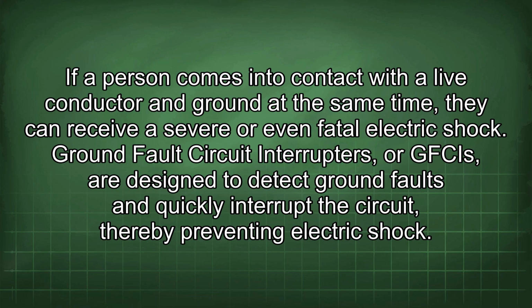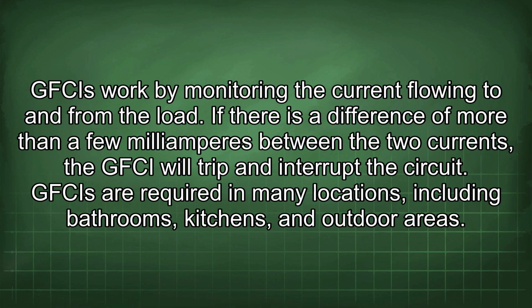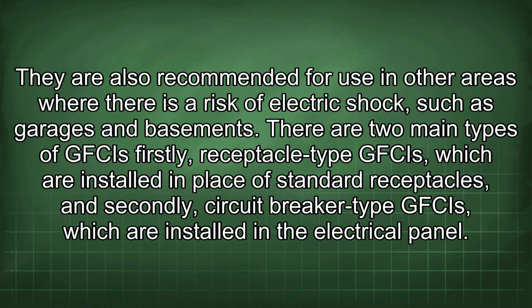Ground fault circuit interrupters, or GFCIs, are designed to detect ground faults and quickly interrupt the circuit, thereby preventing electric shock. GFCIs work by monitoring the current flowing to and from the load. If there is a difference of more than a few milliamperes between the two currents, the GFCI will trip and interrupt the circuit. GFCIs are required in many locations, including bathrooms, kitchens, and outdoor areas. They are also recommended for use in other areas where there is a risk of electric shock, such as garages and basements.